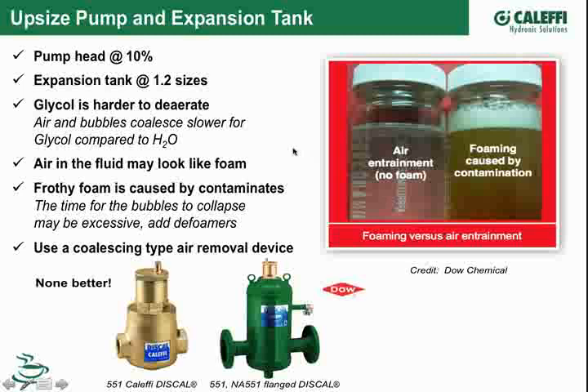How many things go into glycol when you mix it? It's not just one or two chemicals. There's quite a list of things that have to go in there: anti-foaming agents, pH buffer, passivate for the metal, and obviously the base glycol. It depends on the formulation with respect to the application you're trying to serve, but typically you'll see at least 3 and no more than a dozen, somewhere around 3 to 12, depending on what you're trying to do.